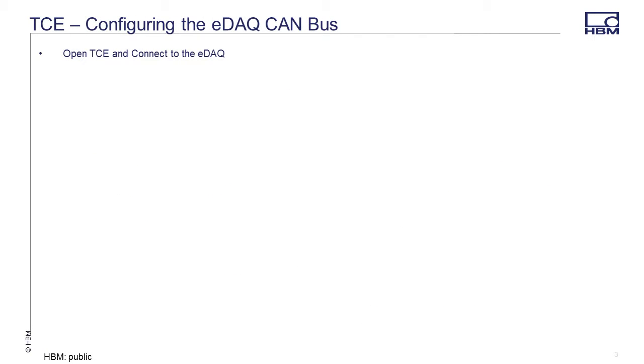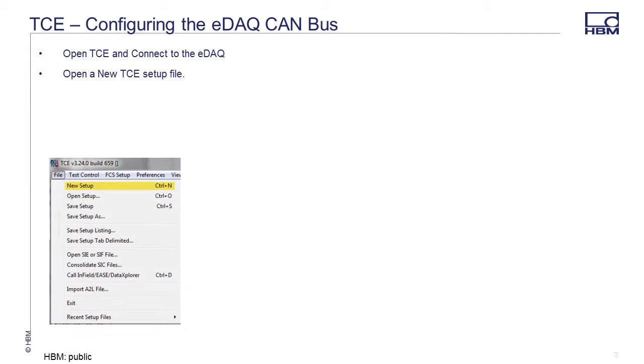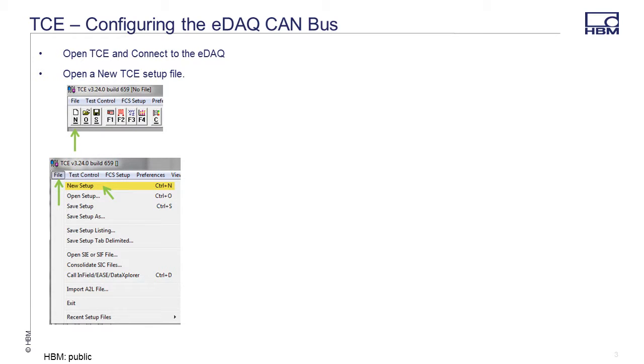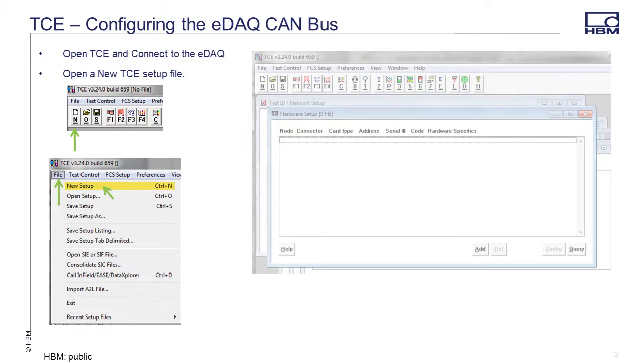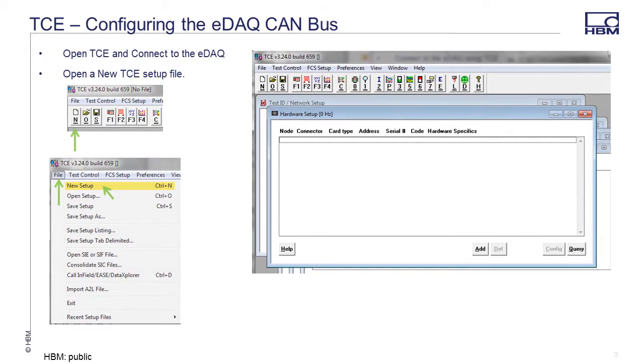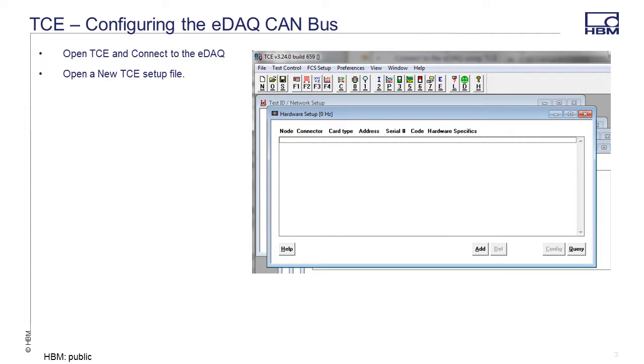To configure the eDAQ CAN port, open TCE and connect to the eDAQ. Open a new TCE setup by selecting the File menu and then select New Setup, or select the N button in the TCE toolbar. Click on the F1 key on the TCE toolbar or press keyboard function key F1 to open the hardware setup window. Next, query the eDAQ hardware by selecting the Query button.